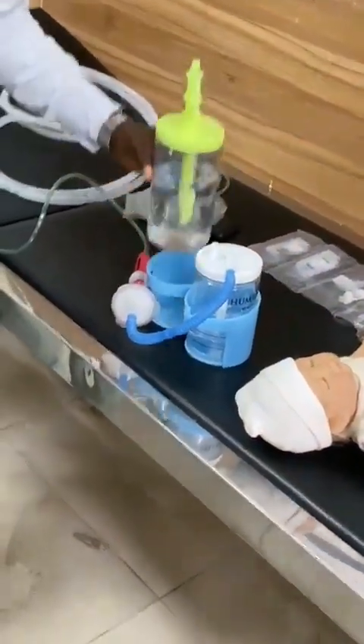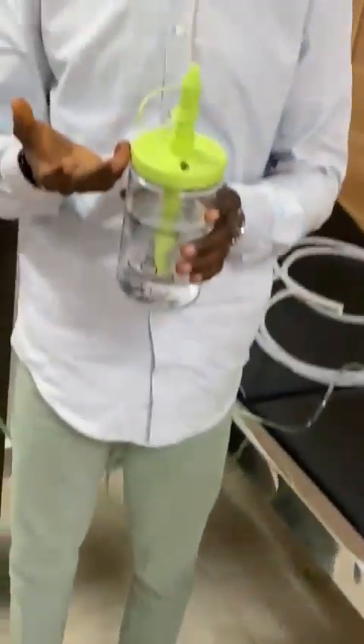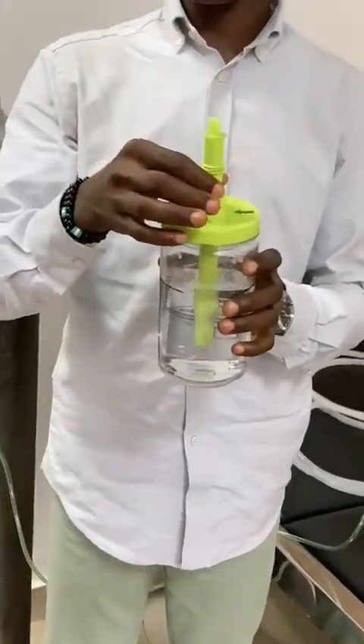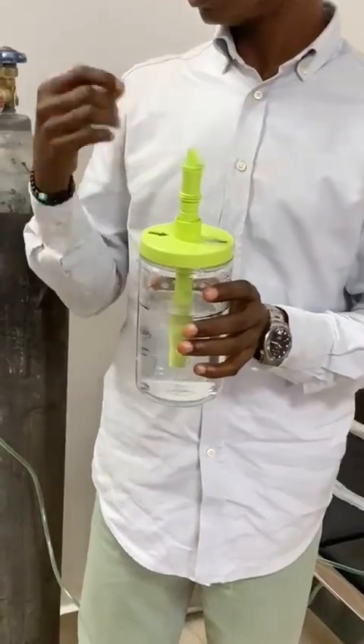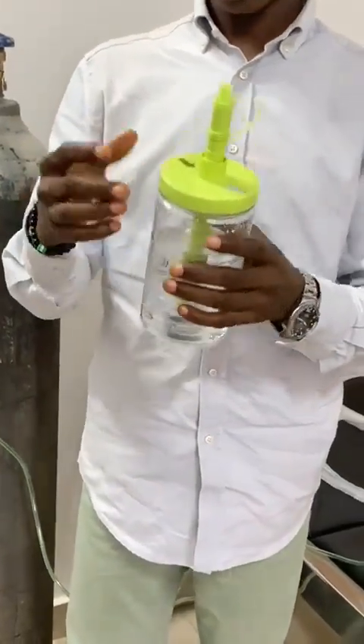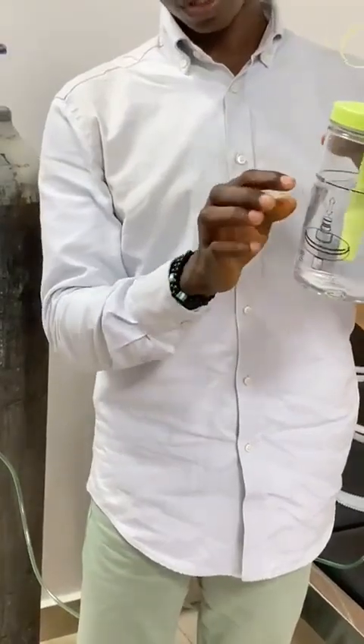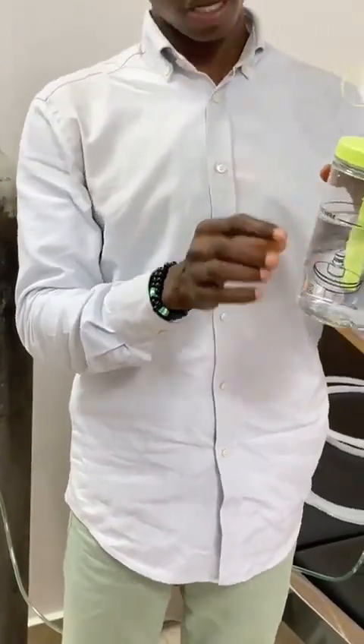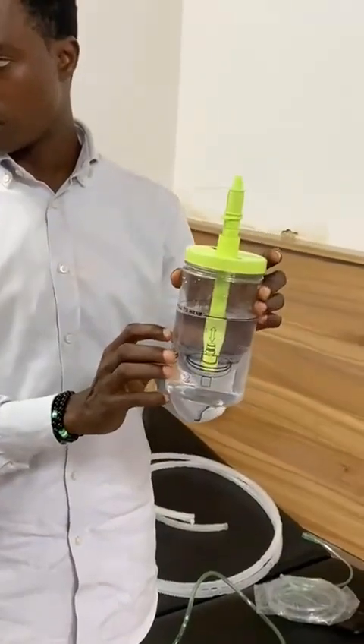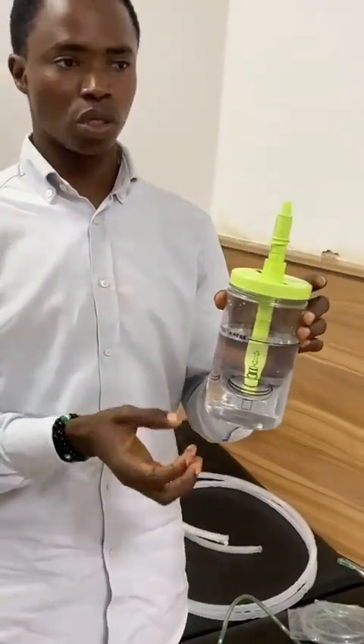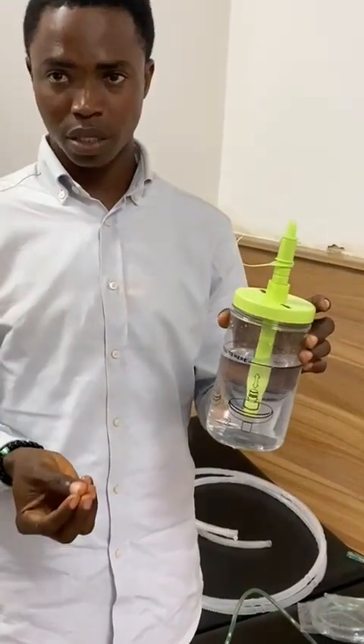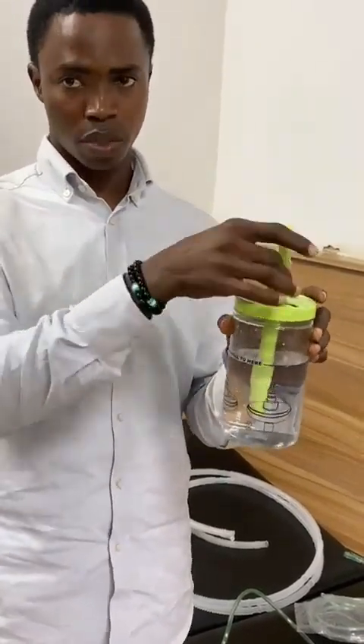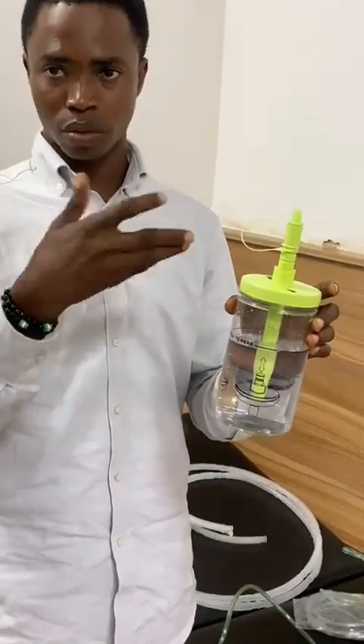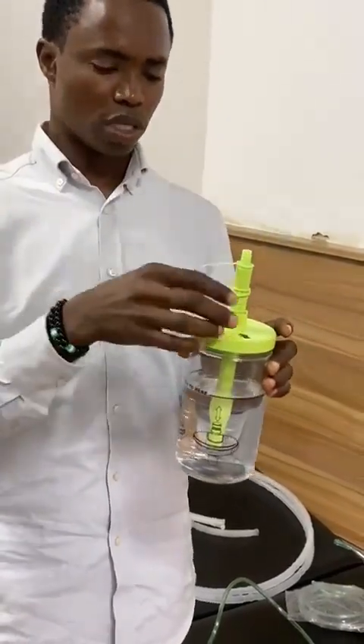So here we now have the bubble bottle. This is the bubbler. This bubble bottle is calibrated from 1 to 10 centimeters of water, and it also has a water level. You can see it filled to this level. The same thing applies here too. If it's too low, the pressure that is generated will not be efficient, and if it's too much, it can also lead to water spilling to the patient.